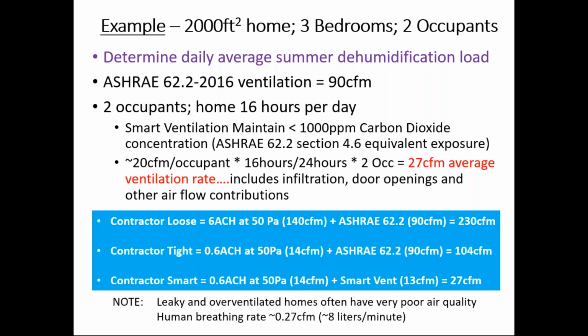And I'll also mention, what's the lower limit? Well, we humans breathe around 8 liters per minute at sedentary or typical sitting, moving around, office-work type activity level. And that equates to about 0.27 CFM. So if we put you in a moon suit and just fed you fresh breathing air, and then your exhaust air would go out directly and not impact the surrounding air around you, we could reduce that 27 CFM by a factor of 100.